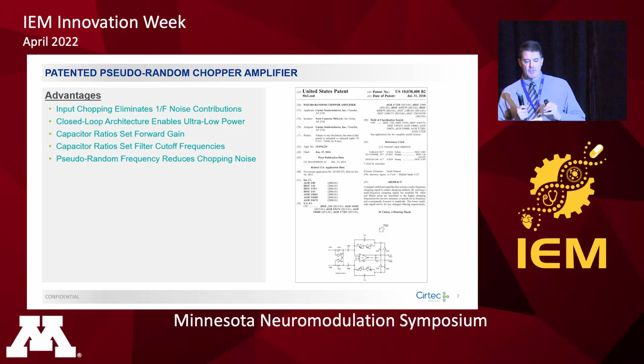In this architecture, capacitor ratios set the forward gain. A lot of times with a forward low-noise amplifier, the gain is set by a single component, and variation in that component leads to variation in your gain. When you use a ratio of components in our IC world, things match very well—the ratio is very well controlled while the absolute value is not. So the feedback cap sets that gain, making it highly repeatable.